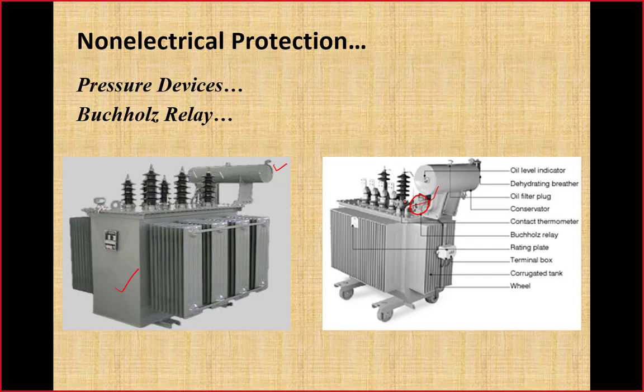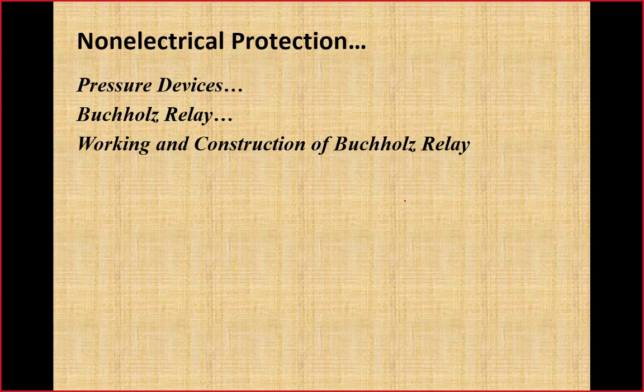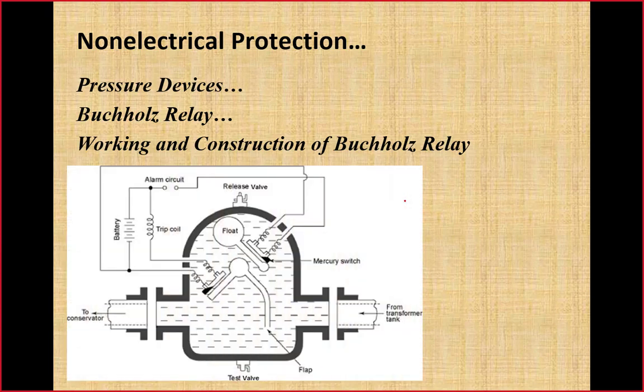So it means when an explosion takes place within the tank of the transformer due to a short circuit fault due to damage of insulation, then oil decomposition will create a pressure wave. Oil will be pushed into the conservator through this Buchholz relay, and here the Buchholz relay is to sense that pressure wave created inside the transformer tank. Now here we will discuss working and construction of Buchholz relay. So this is a schematic diagram that will help us to discuss its working as well as its internal construction.